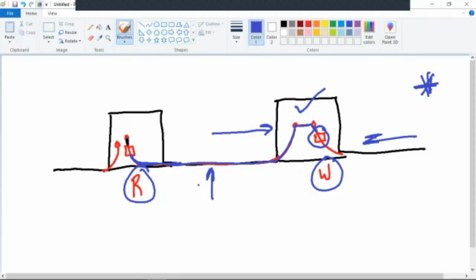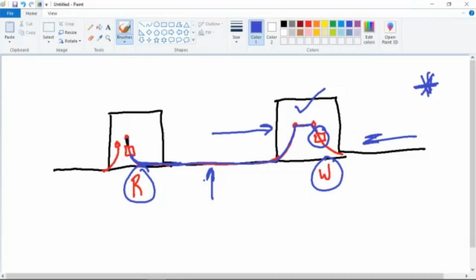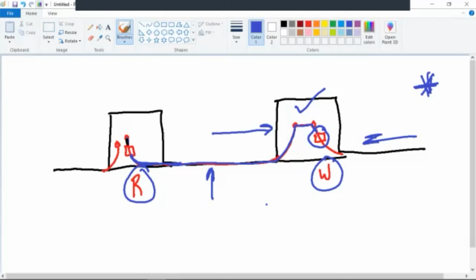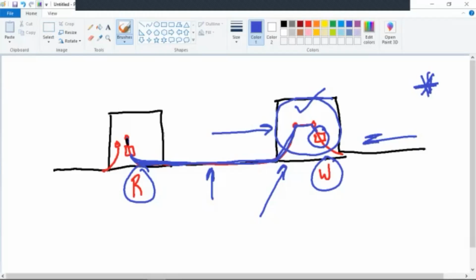All right, there really is no method. We did have a piece of equipment that we were able to carry around and test three-phase transformers with. We only had one, and it was very, very expensive. You're not going to typically, unless Professor V, you've seen them happen regularly. We did not. You're not going to test transformers. Right. A transformer tester is very expensive to test windings and everything inside a transformer. I just want to give you guys the heads up and knowledge that not only is the indicator looking at the conductor itself that's going through the span, it is also monitoring the whole transformer itself. And you may have the possibility of a bad transformer. Rare, but it has happened before.